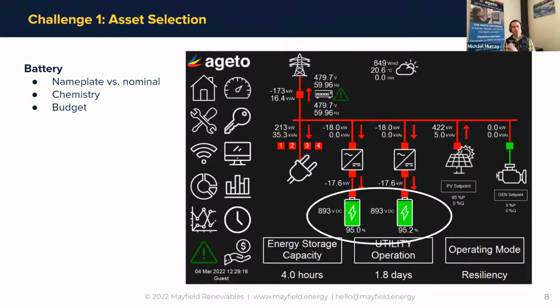There's kind of two C rates, depending on the sizing of the system. There's a battery-rated C rate, which is the max it's rated for, but then there's the installation's actual C rate. So you can have 300 to 400 kilowatt hours of battery behind a 100 kilowatt inverter - the battery system in that case would be 0.3 C, but the batteries might be rated at 0.5 or 1. You just want to make sure you don't overload the batteries with the inverter.